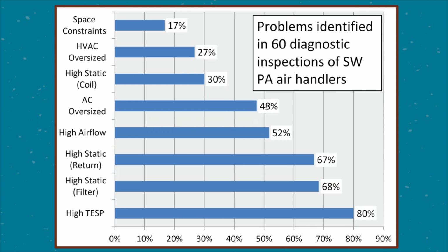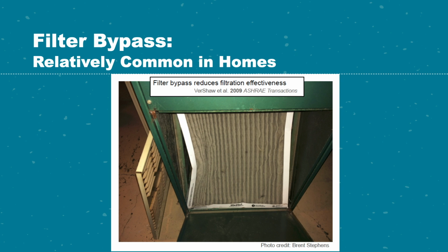Obviously, it's more common in an AC system than a heating system. But another issue is that no matter what filter you've got, if you've got a filter bypass, and ironically also if you've got leaky ducts, your static might not be as high because it's not restrictive, but it's also not working. So this is something just to check on next time you stick in a new filter: gee, is it a good fit?